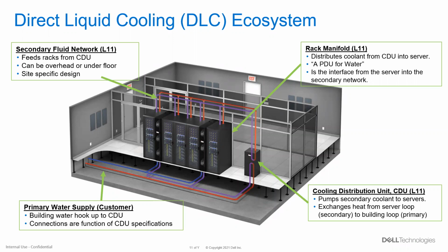The facility water loop doesn't really need to be as clean or highly filtered. It's going to be typical facility water that doesn't require the customer to do anything above and beyond what they would normally use that water for. But by capturing the IT heat and rejecting that heat to the facility water, which is then taken out to either evaporative towers, cooling heat exchange methods of some sort, you've got an environment that leverages a very high level of efficiency at extracting the IT heat and removing it from the data center.